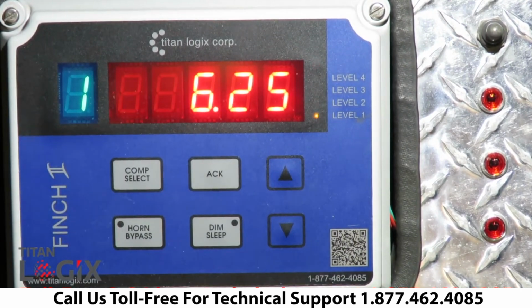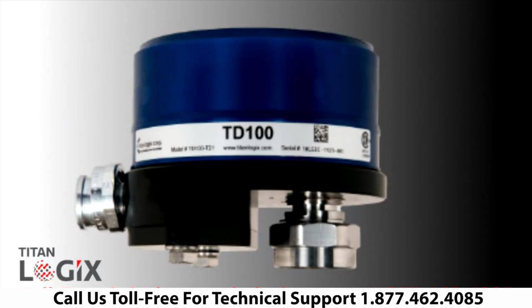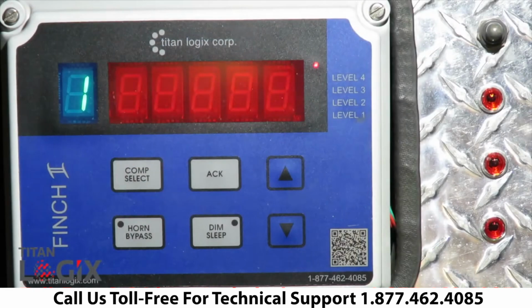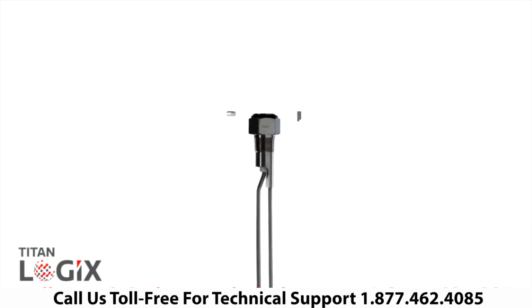There are several reasons that could cause the E20 code. The most common cause of the E20 is when the transmitter is loose on the probe. This can be remedied by tightening the large nut under the transmitter. Another cause could be the shorting of the probe above the spill level, which is 0 to 7 inches below the probe threads. Check for debris attached to the probe.